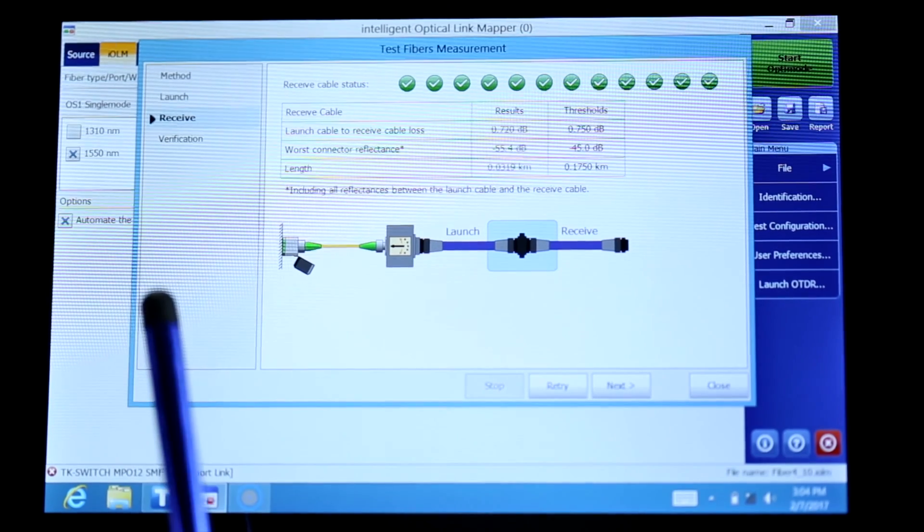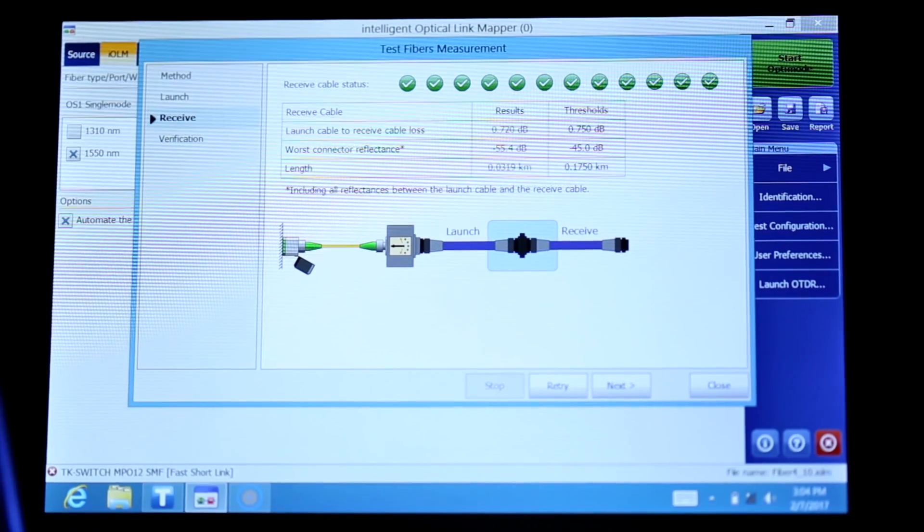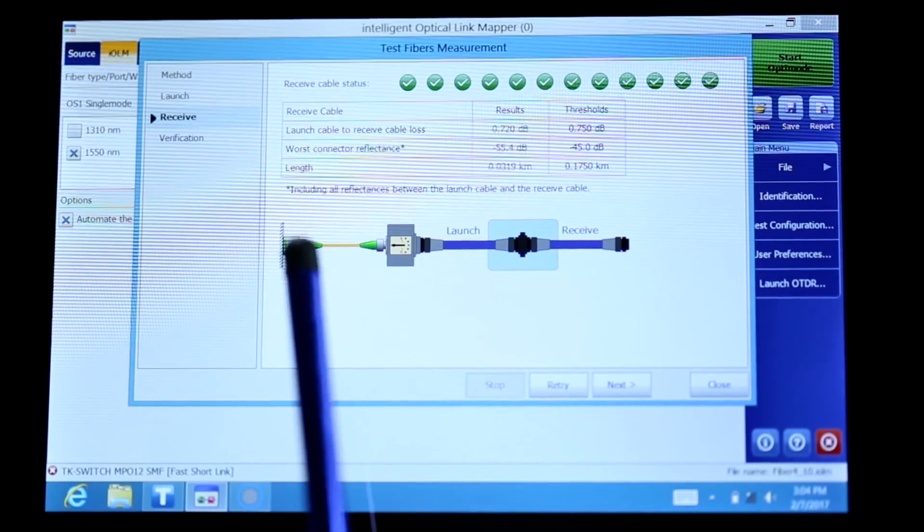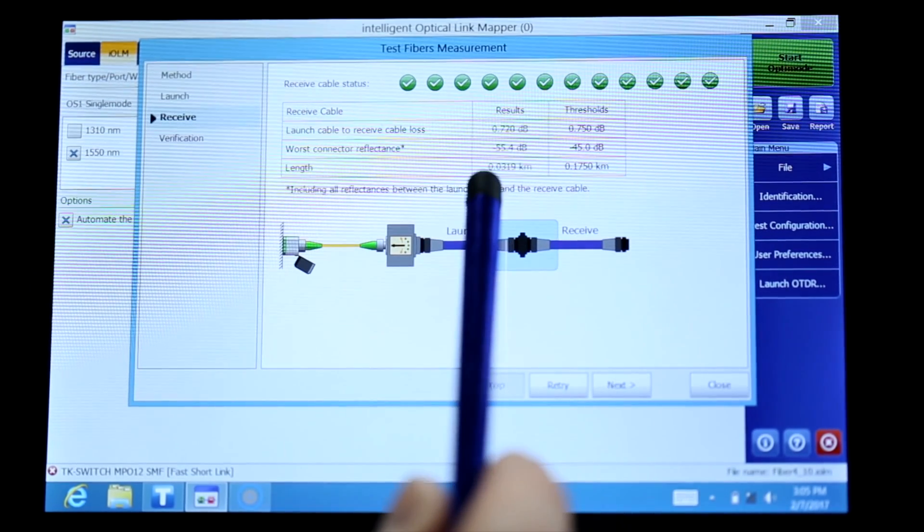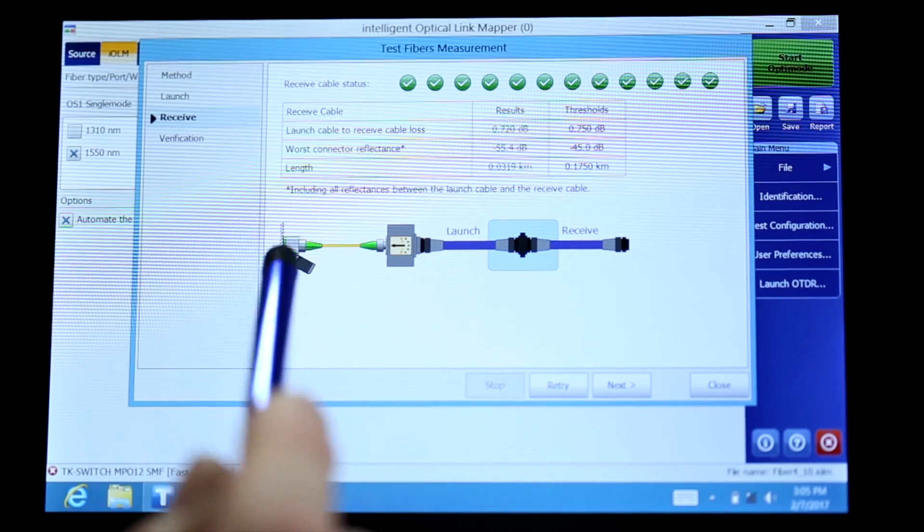What we see here is the successful completion of the 12 fiber that have been tested. You see the green round for each fiber with the check mark indicating that each fiber has passed. In this test, the launch and the receive connected together, measuring also the connection, the MTP connection between the launch and the receive. In the result tab, the worst case of the 12 fiber, the worst case has been 0.72 dB for one of the fibers and minus 55 dB for the reflectance.